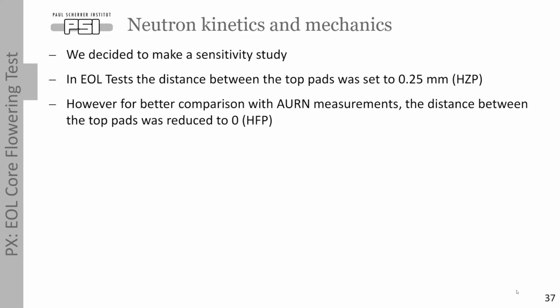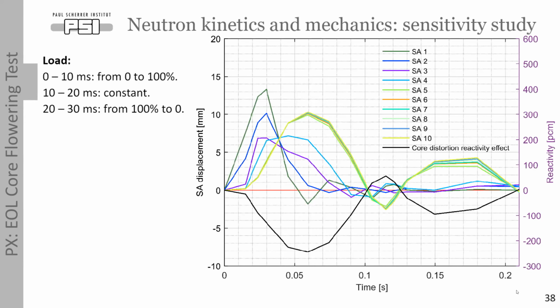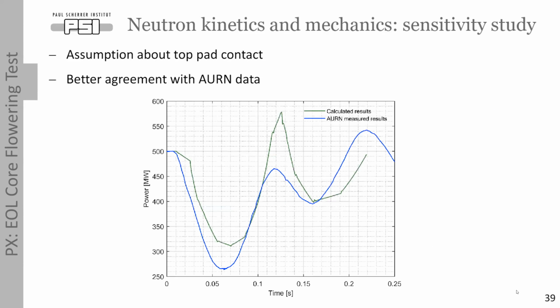And this resulted most likely in closure of the gap between the pads, because expansion at the top was higher than at the bottom. So we repeated our calculation, but now with zero distance between top pads, so all assemblies were in contact. And this is the result: we see similar deformation qualitatively, but quantitatively the pattern was quite different. And now we compare the resulting power with our measurements, and we obtain even better agreement.